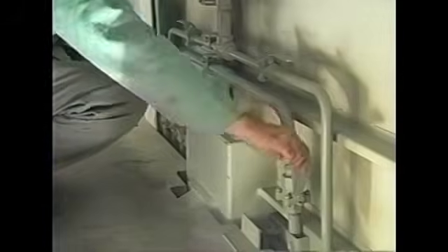Close the return valve to the leaking compartment. Close the supply valves on the other compartments and run the fuel pump until the leaking compartment is empty. When the leaking compartment is empty, close the supply valve for that compartment and open the supply valves to the other compartments.